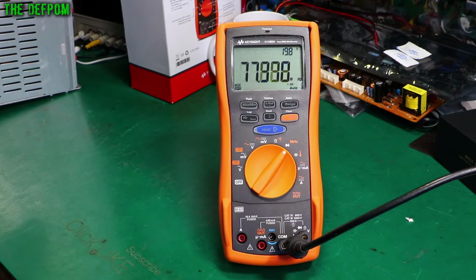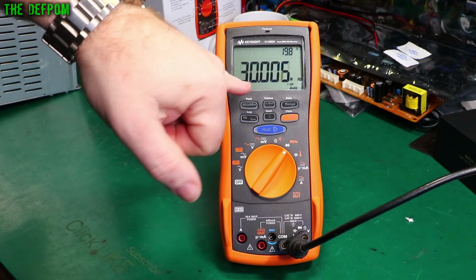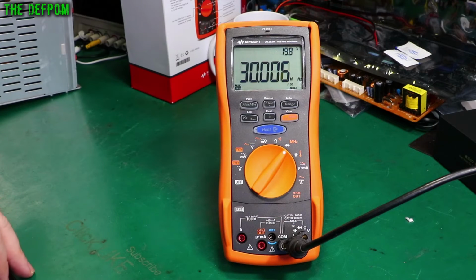So I go 31, and I increase my RF level a little bit. Let's go to, say, 300 millivolts. Is that enough? No. 500. No. 800. Nah, so 31 megahertz right now, I can't actually see it. So back down to 30 megahertz again. Can't do it. Okay, I have to drop the level back down to 100 millivolts. 200 millivolts, yeah, okay. So 30 megahertz, even that is being a little bit glitchy. So 30 is like the very top end of what this thing can actually do.